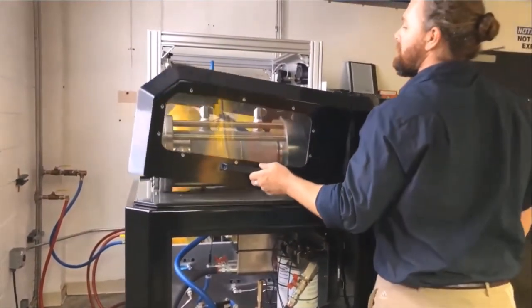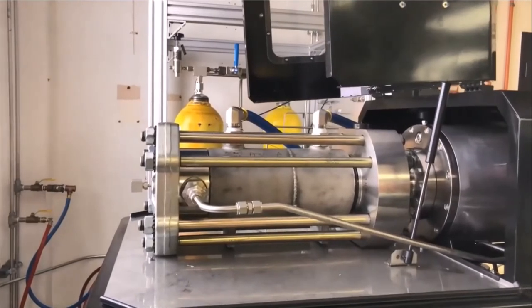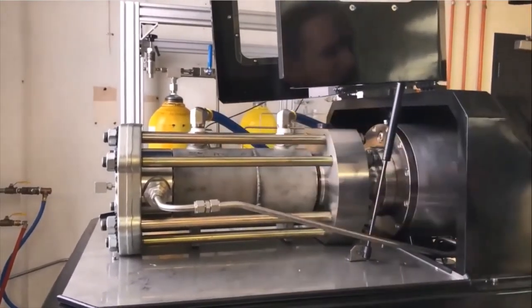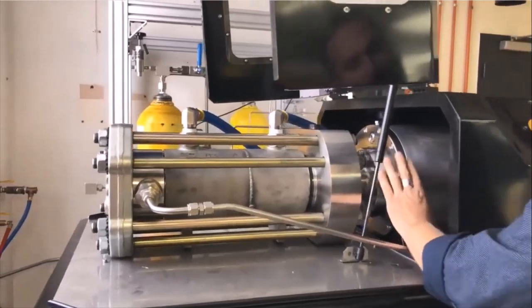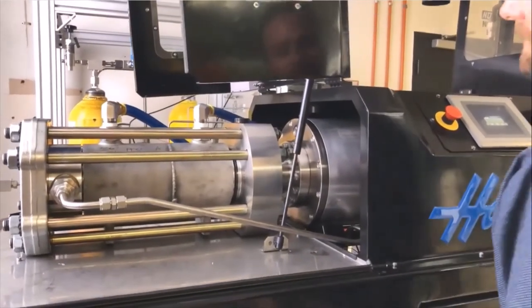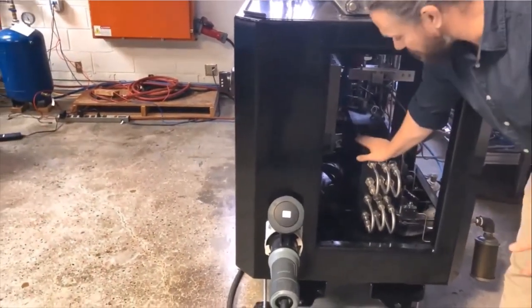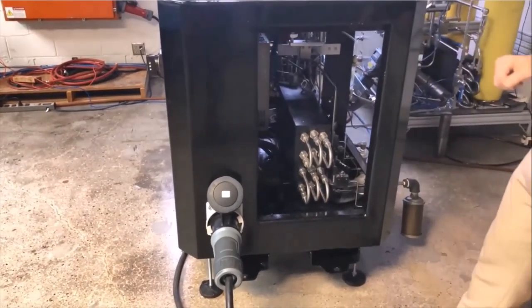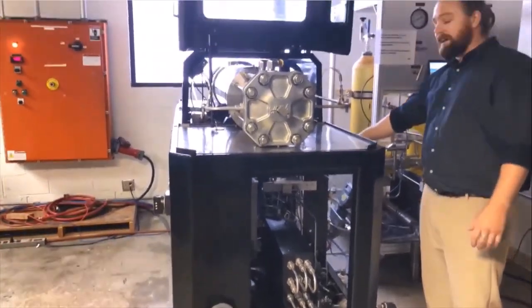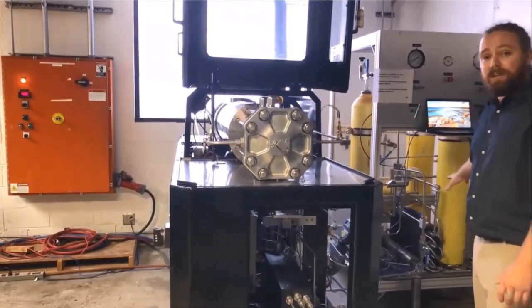Up top here, let's go through the gas sections. Right now we're looking at a single stage double-acting gas booster — this is the QGD 90. Here's your cooling circuit going through the cooling jackets, your servo drive, and our distance piece gas section. The distance piece ensures there is no oil getting into your gas section; the oil is operating at lower than 30 PSI. This is the heat exchanger — we can use this as a pre-chiller or an after-chiller. In a two-stage configuration, we take the first stage, store it inside an interstage vessel, cool it down by the heat exchanger before it enters the second stage, and then downstream to your application.